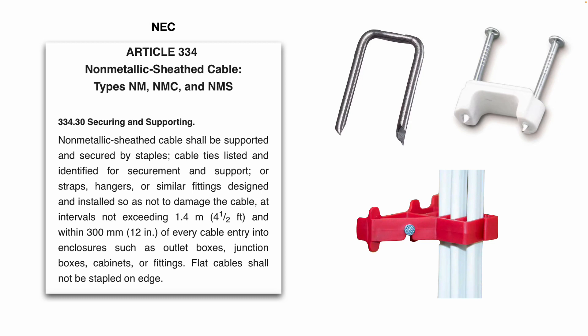Or non-metallic sheath cable. The images on the right-hand side show the different staples that are available to secure Romex to a 2x4 stud. You want to make sure the cable is secured within 12 inches of every cable entry into enclosures, such as outlet boxes like we're going to be installing today.